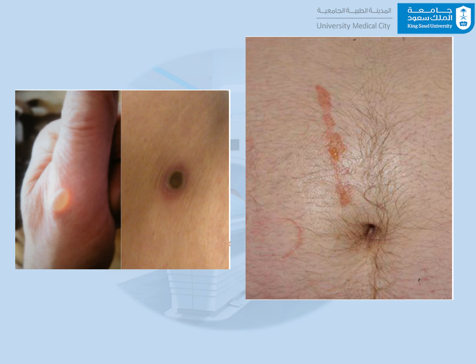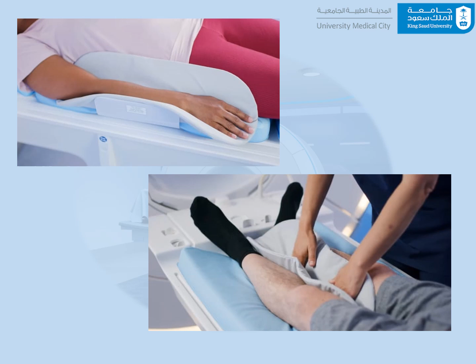Defective RF coils can potentially cause localized burns, so proper separation between the patient and the magnet bore must always be maintained. Appropriate positioning devices should be used to ensure the safety and comfort of the patient. Care must be taken to ensure that the patient's clothing and any coils do not hang at the patient table.